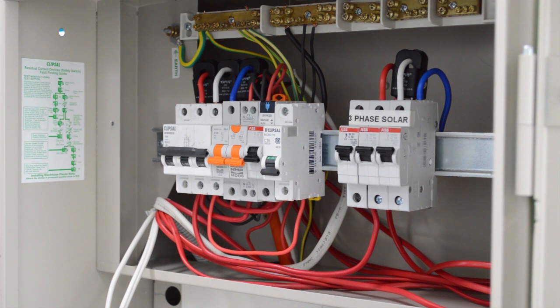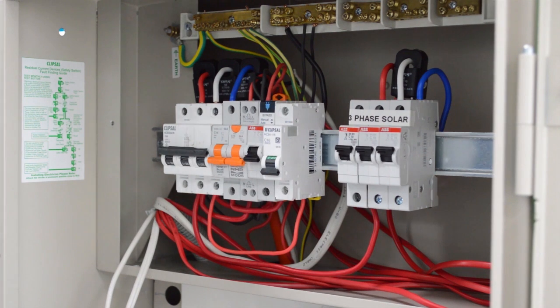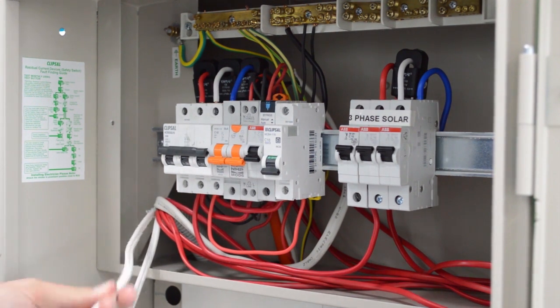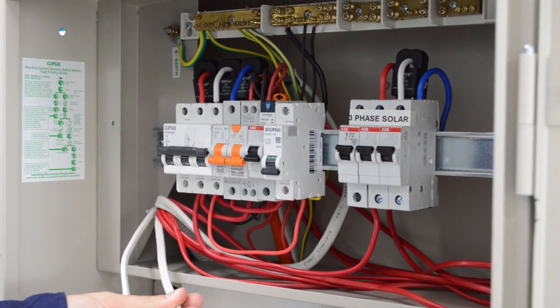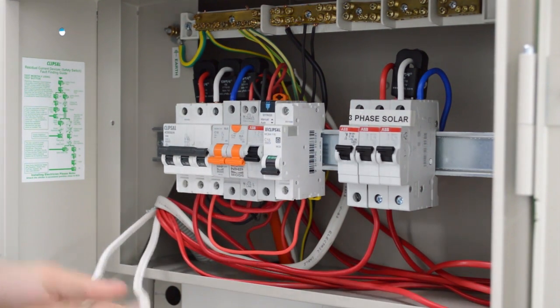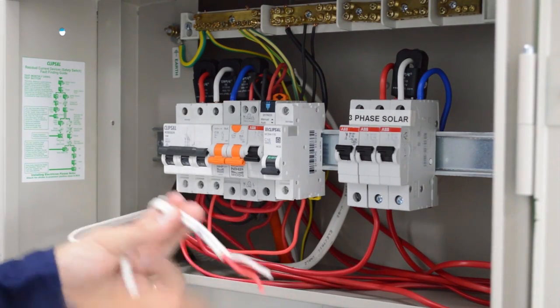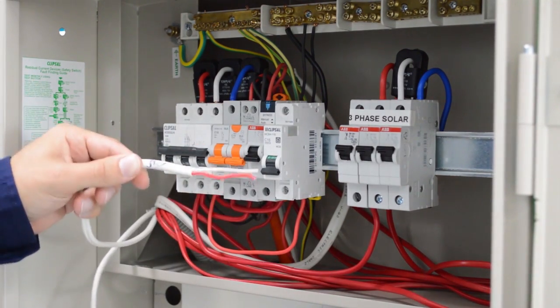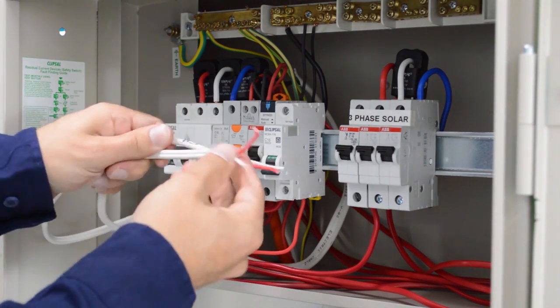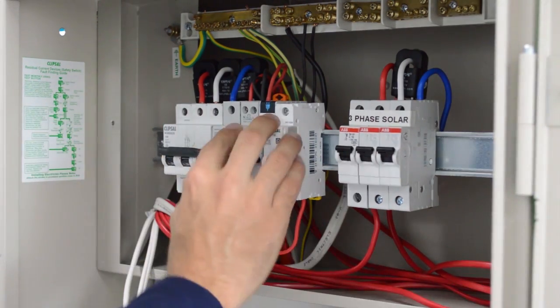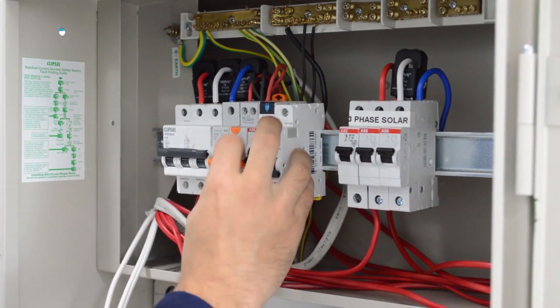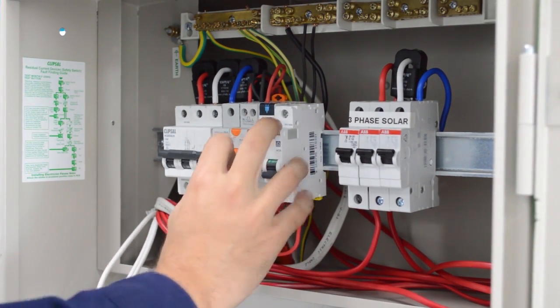Bypass switches must be installed for each switch in parallel. First, we're going to start by running a suitably sized twin active cable, 1 per switch and 1 per bypass switch if an external weatherproof switch is required. So firstly, I'm going to demonstrate the switching bypass with a weatherproof bypass switch. This means I have run a twin for the switching bypass and a twin active for the carbon track relay. For the purposes of this installation, I'm going to be switching the lighting circuit breaker.